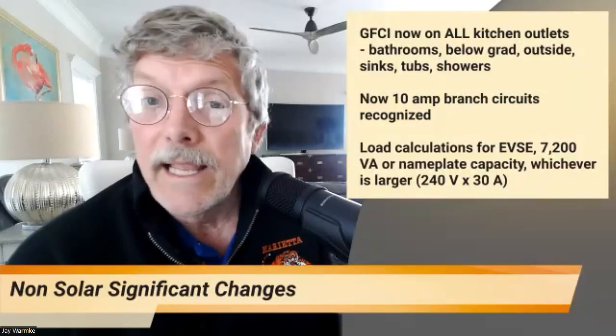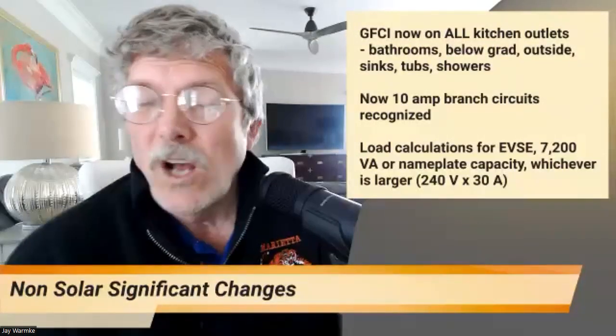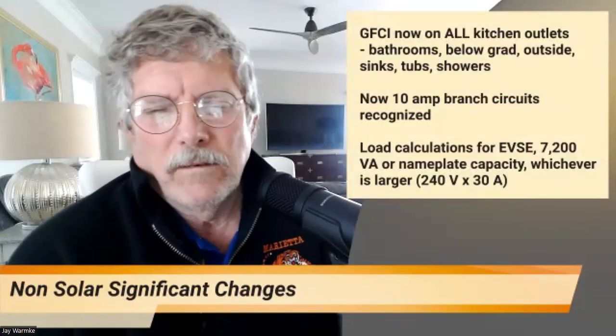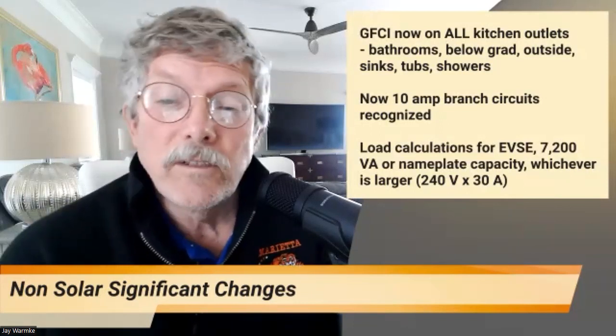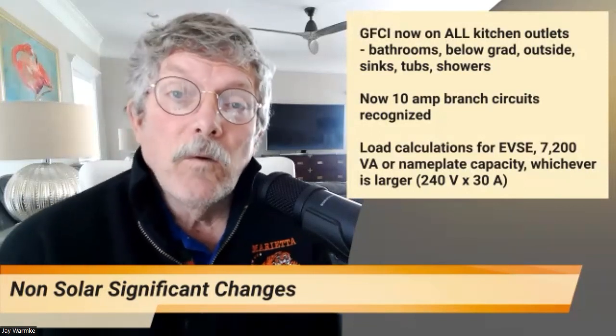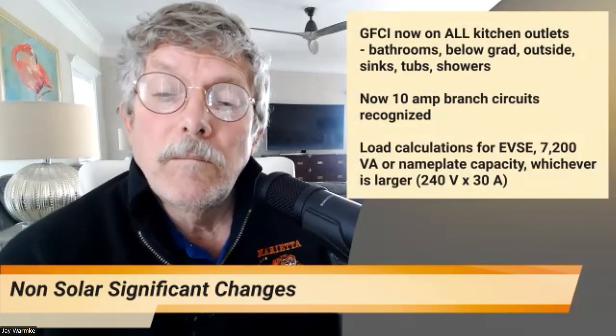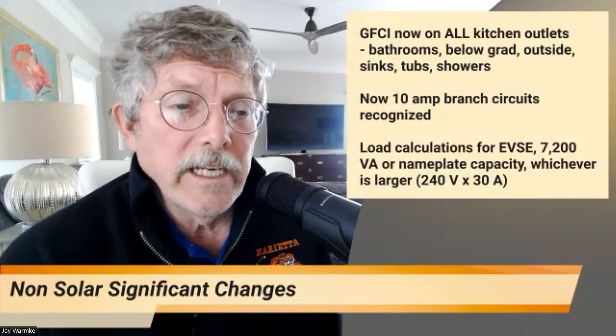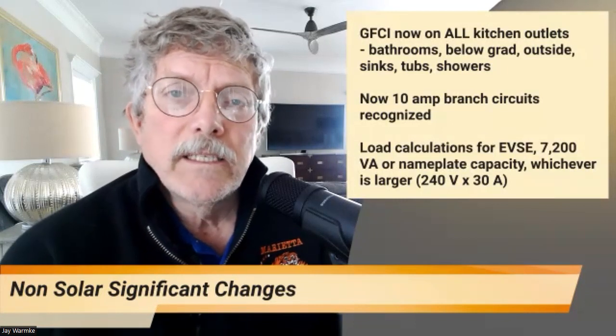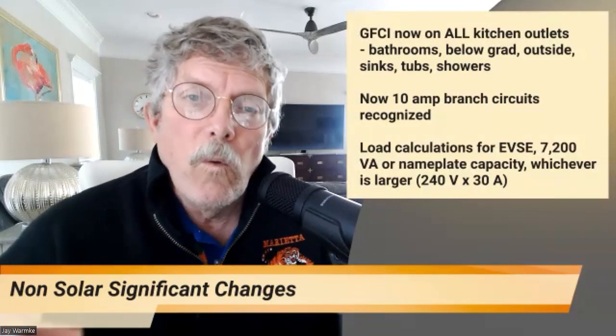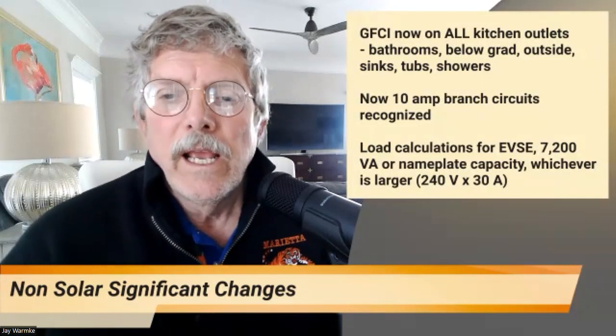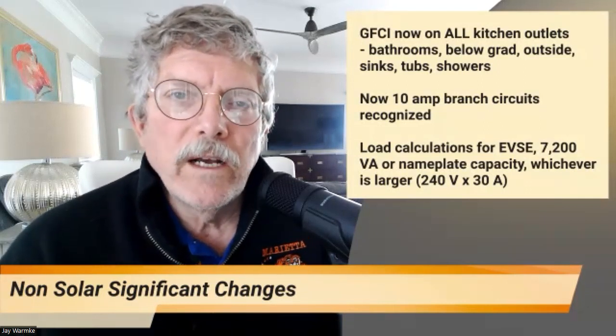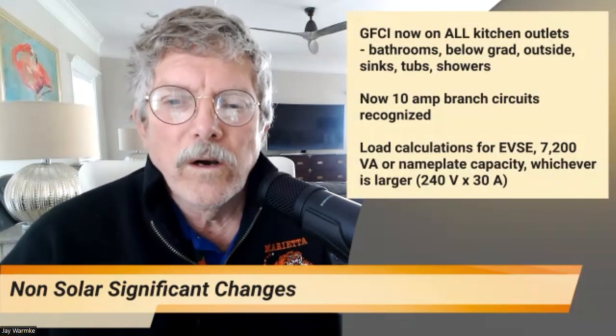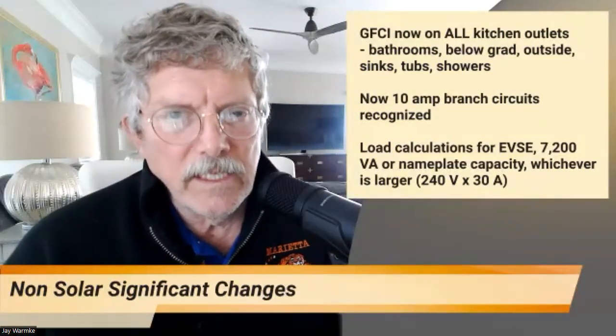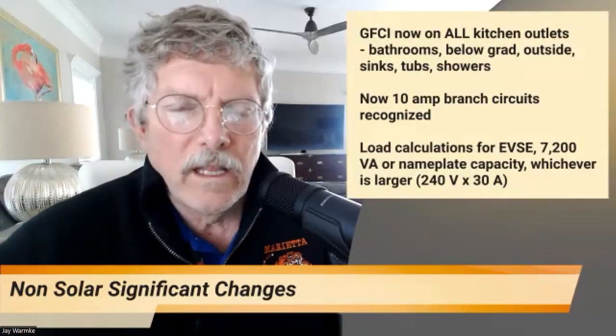specific cases, like lighting. I think another one was exhaust fans. That could be a 10 amp circuit. There was one other one, but I don't remember what it was. But anyway, that's just interesting that they've done that. And something that we're going to be faced with: electric vehicle charging stations. What they've added into this code is that when you wire a charging station, it has to be rated for 7,200 volt amps or the nameplate capacity of the system that's being installed, whichever is larger.